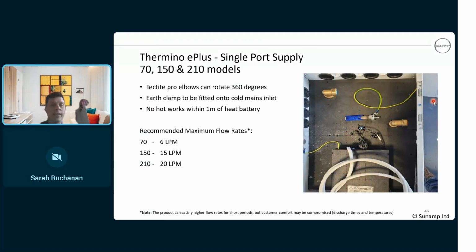Moving on to mechanical connections - someone mentioned an EPV earlier. On the previous models of heat battery, the pipework changed depending on the application. Due to popular demand, we've now universalized the pipework connections. So with the ePlus, whether it's working off grid electric or PV, you're going to have one pipe in, which is your cold going into A, and your hot pipe coming out of D at all times. That's your pipe connections with the ePlus always.